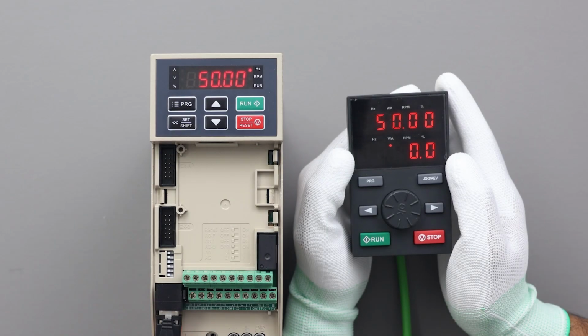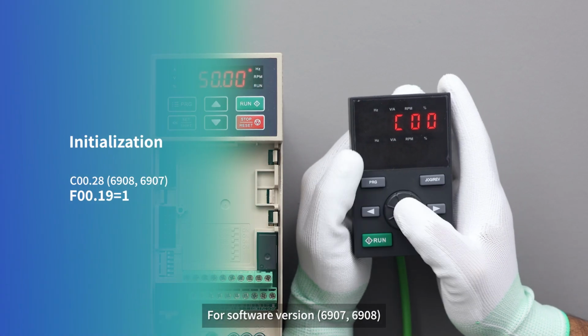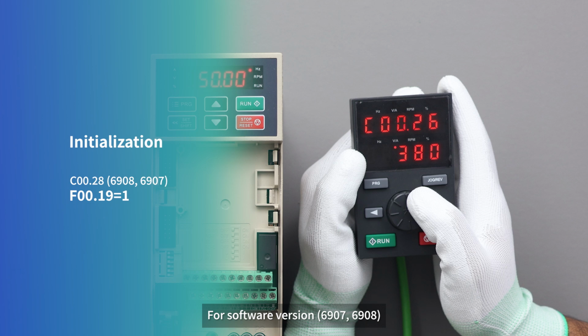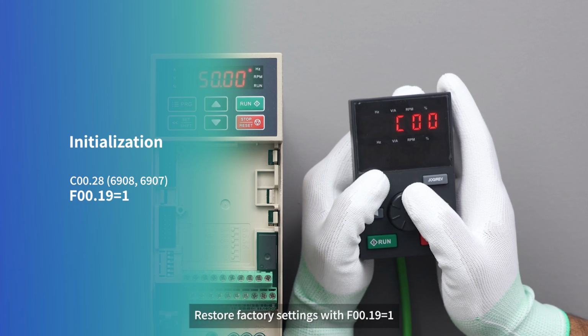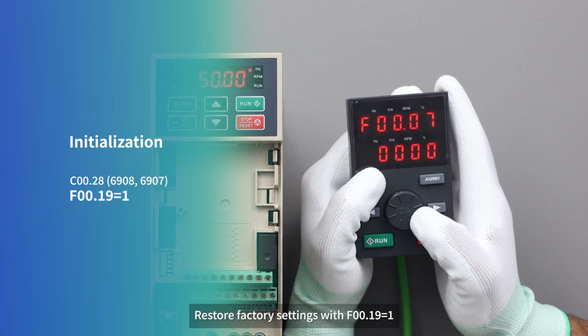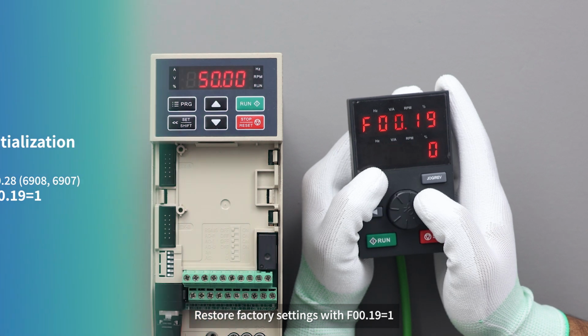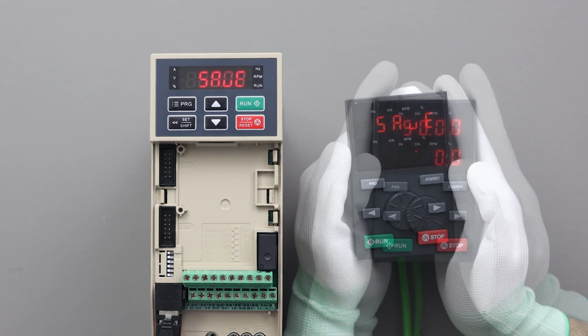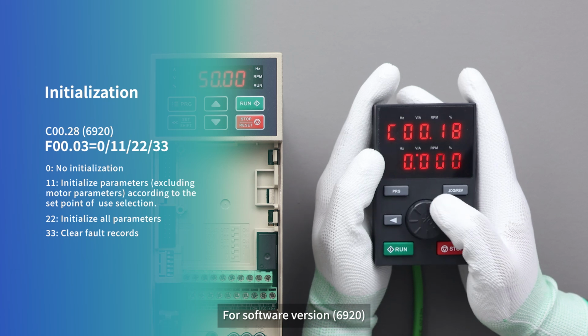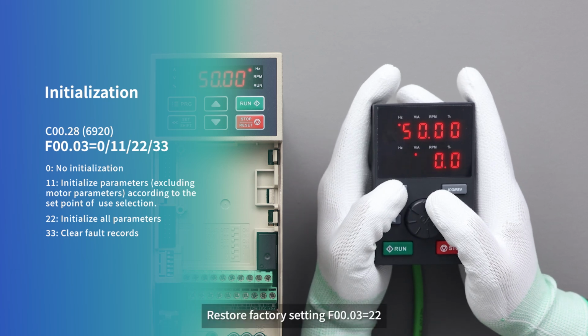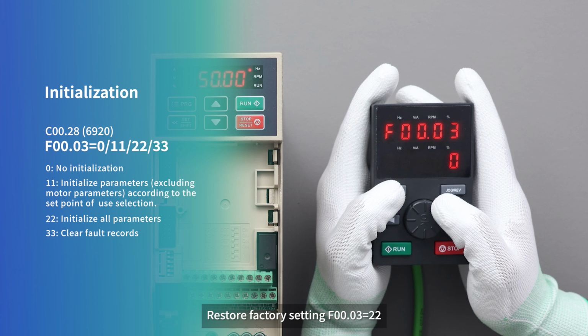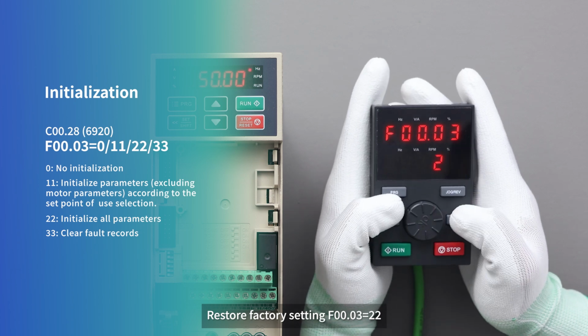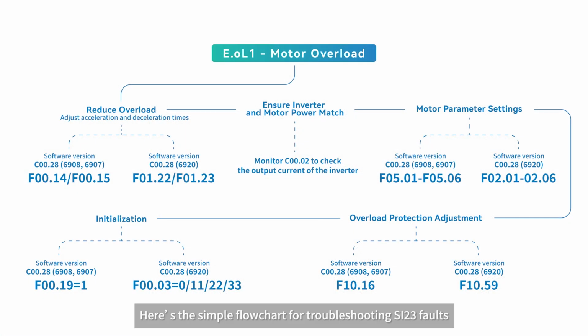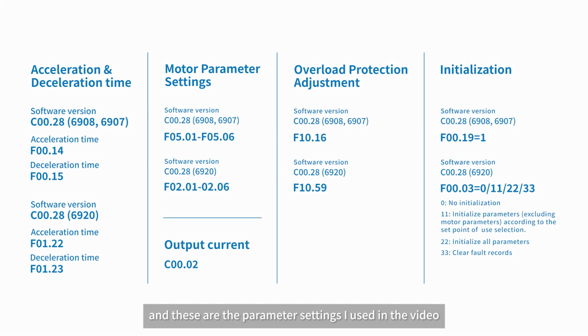Factory reset. For software version 6907 and 6908, restore factory setting with F00.19 to set 1. For software version 6920, restore factory setting F0003 to set 22. Here is the simple flow chart for troubleshooting SI23 faults, and these are the parameter settings I used in this video.